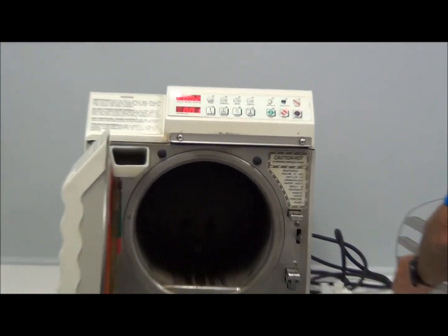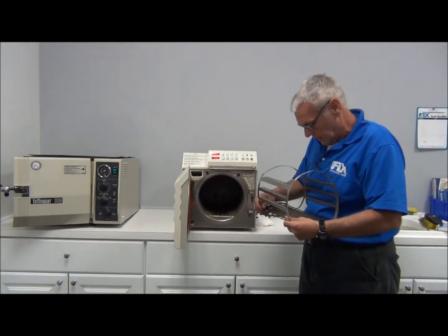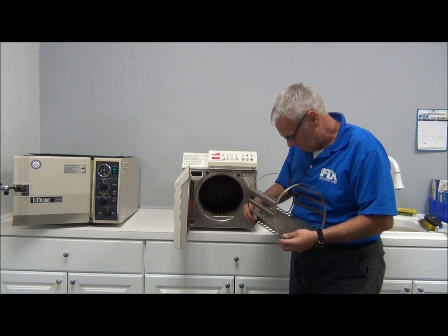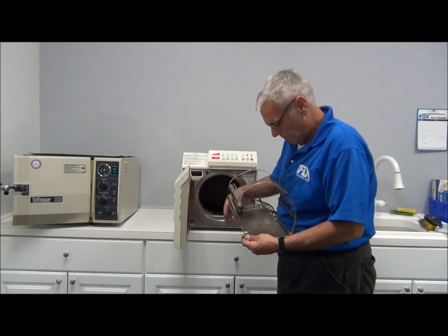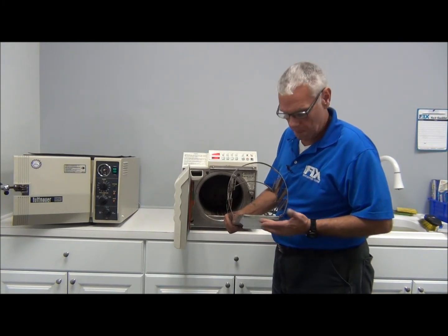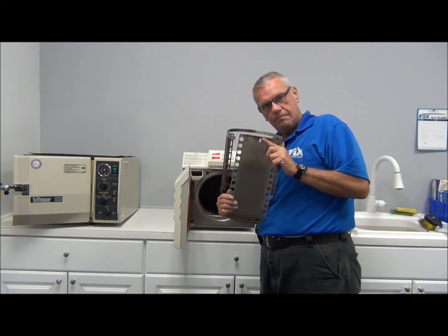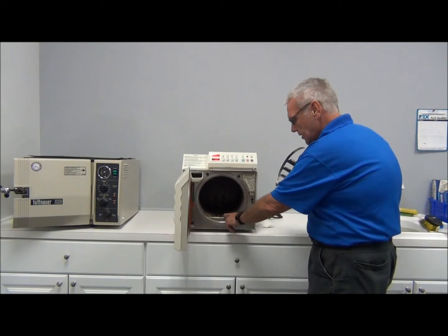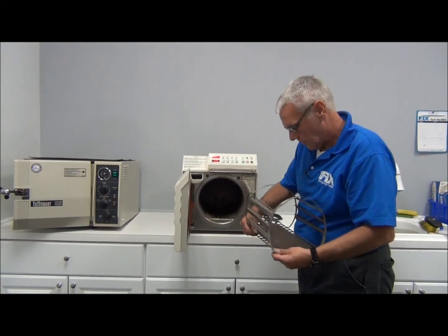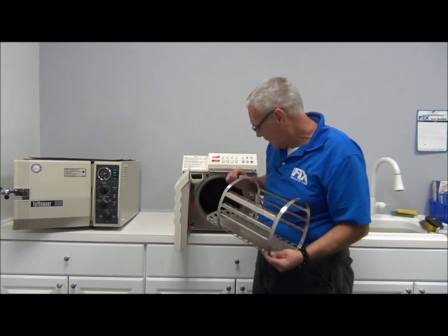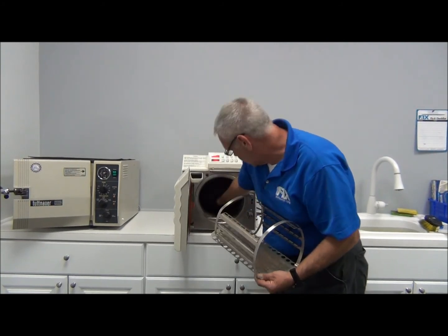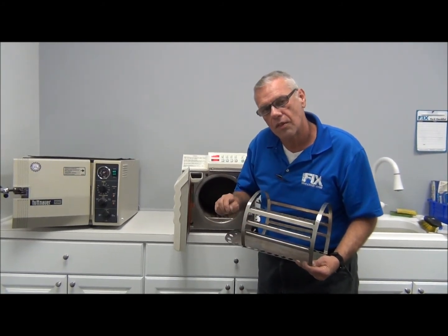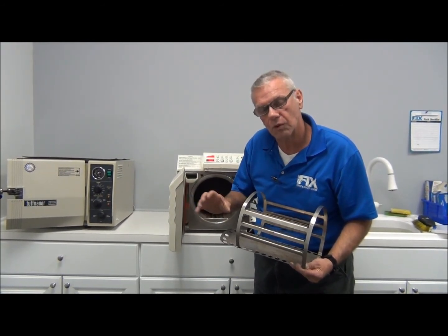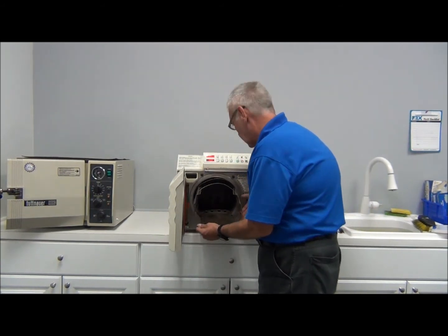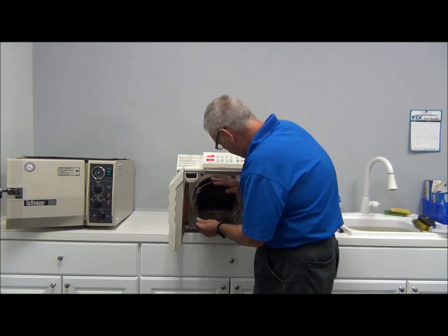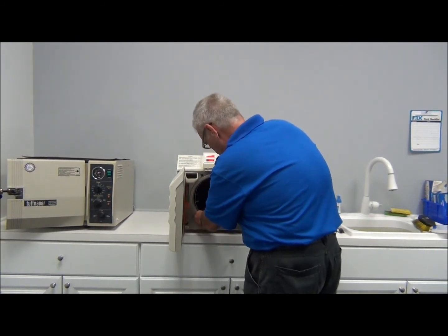Now we're going to reinsert the tray rack. Ladies and gentlemen, this is probably the most important part in the preventive maintenance procedure. The tray rack has a lip on the front and a catch under it. As you can see by my finger, the lip and the catch correspond with the front lip on the sterilizer. The rear of the tray has a flange that goes up to ensure that it doesn't touch the temperature probe or the fill line regulator or the water sensor in the machine. So you stick this in and compress it as you go in. Lift up, and there we are.